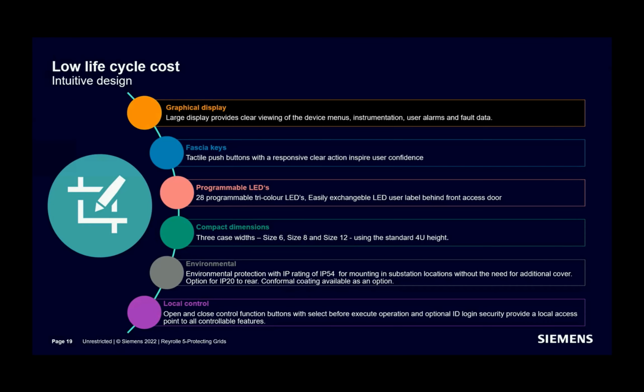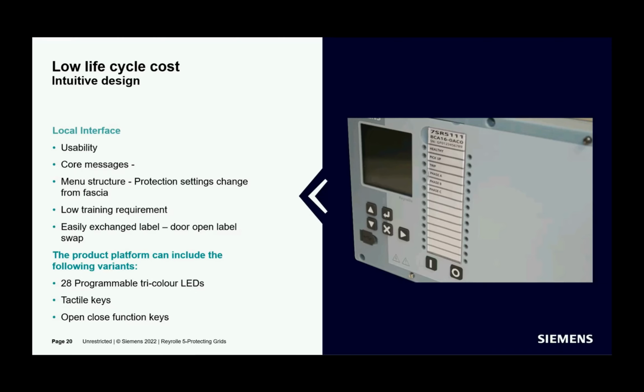Now, more detail about low life cycle cost here. Let's have a closer look at the front face. As you can see, there are 7 push buttons here, 5 of which are used for navigation inside the fascia menu to have full control of the device. What I mean by full control is that you can navigate through all the device settings, device status information such as binary input, binary output, LED status and communication status. But also, it is possible to check all the process records such as events, faults, pickups. But again, full control here.